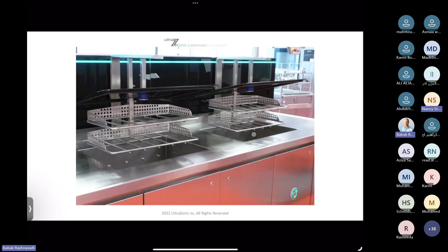So this is the device. Here you can see a part of the device where, on the left side, even in the sink there are sprinklers, which really clean, flush and rinse all the instruments. On the right side you have this ultrasonic device. But we will go into more detail on the next slide. This is the spray sink, and you see the bottom is in a V shape. The V shape is very useful because you don't have to clean all the time and get all the dirt out of the bottom with your hands. This is all automated. When you have a heavy duty cleaning with all these sprayers, the lid closes and it all happens in the sink itself. And the drain is big enough to drain all the dirt through. Next, please.